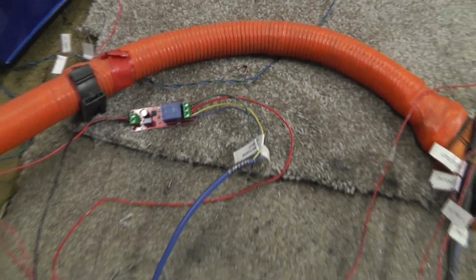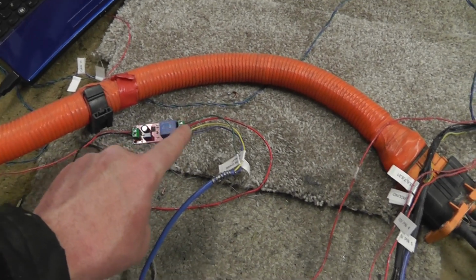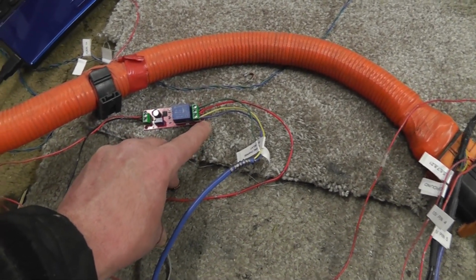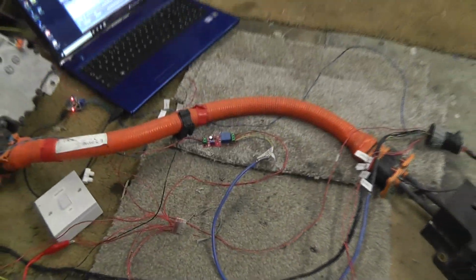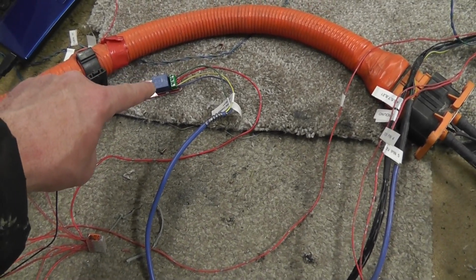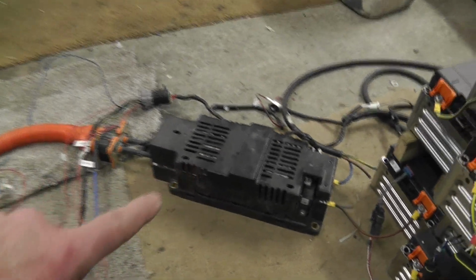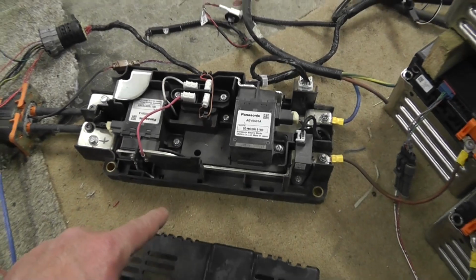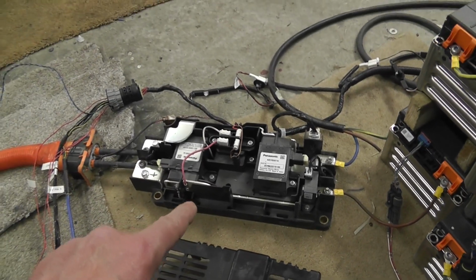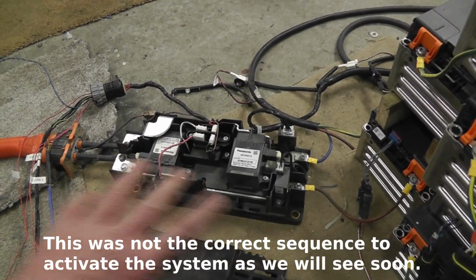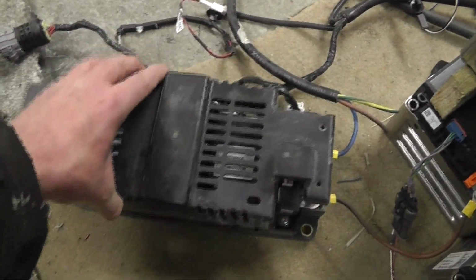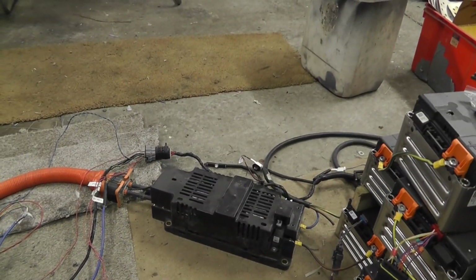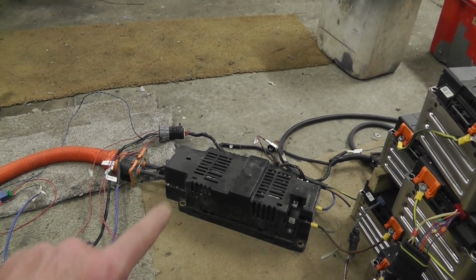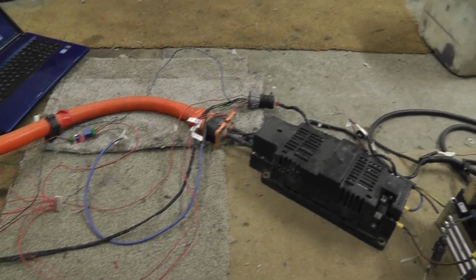The timer relay, when the 12 volts comes through, goes to one side of that unit for about 2 seconds, which puts 12 volts to the contactor that has the pre-charge resistor on it. Then it flicks over, and the 12 volts goes to the two main contactors, which send the 350 volts DC directly to the DC to DC converter. So it triggers the 350 volts to go through the pre-charge resistor first, then flicks over to the main contactors.